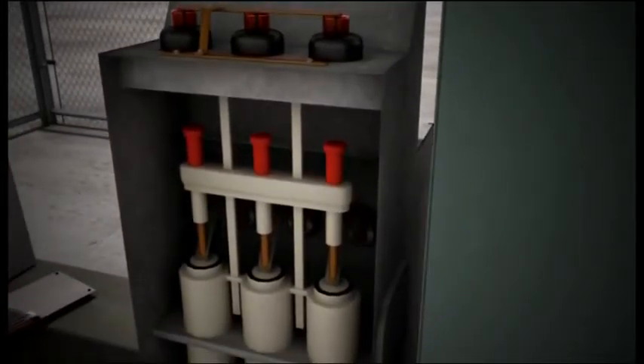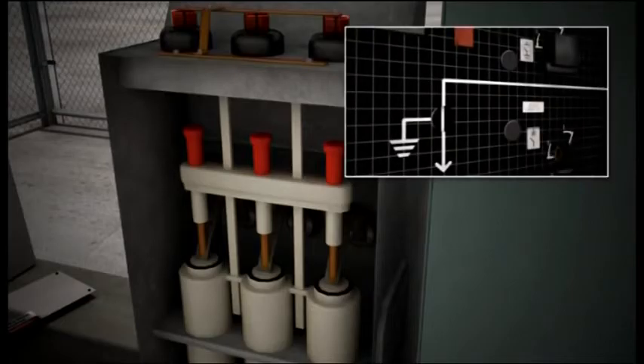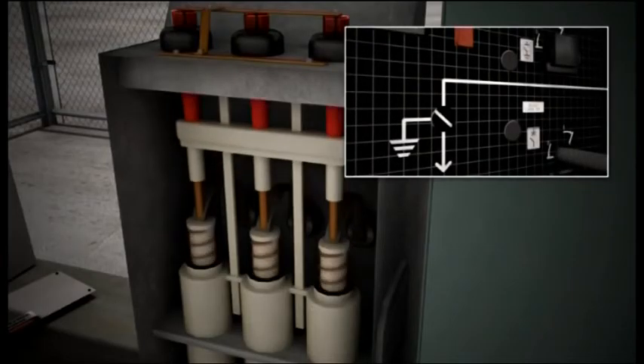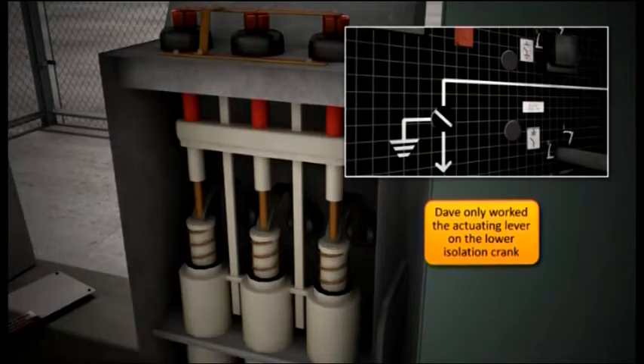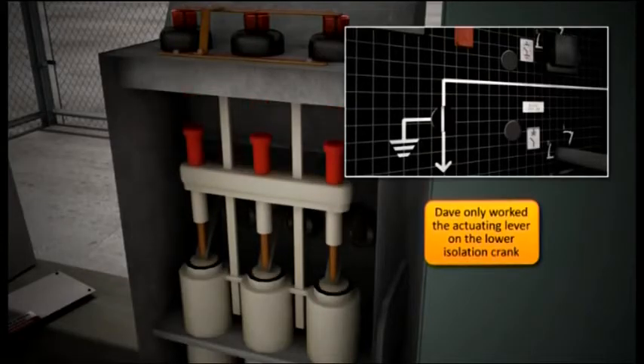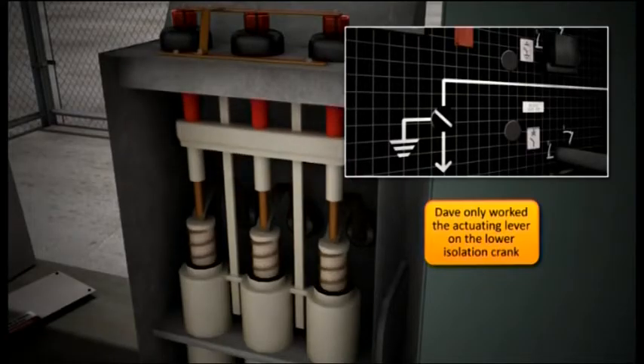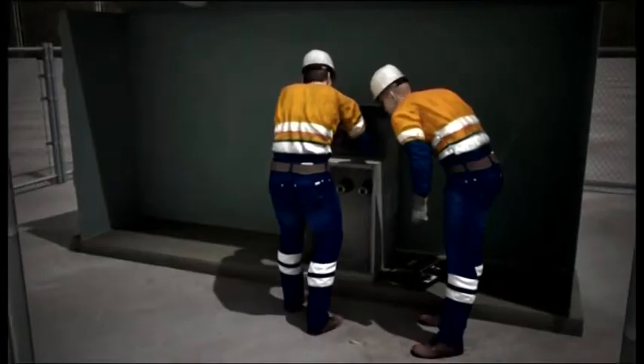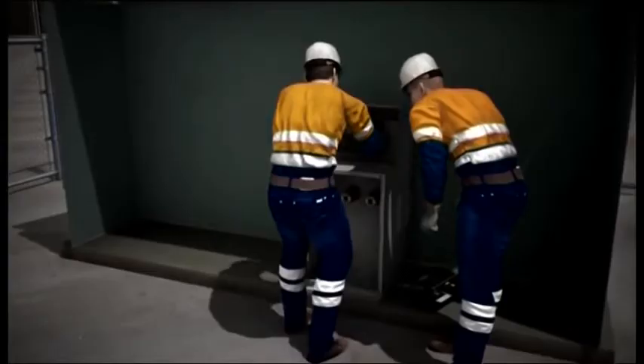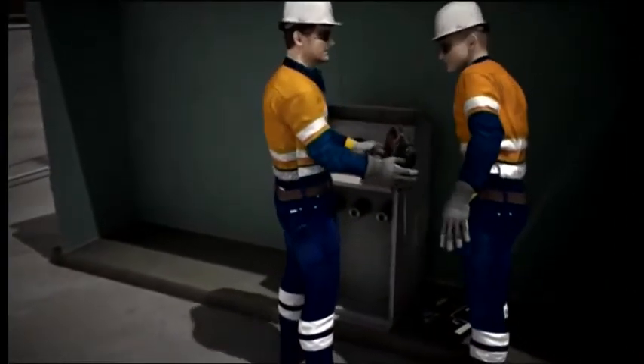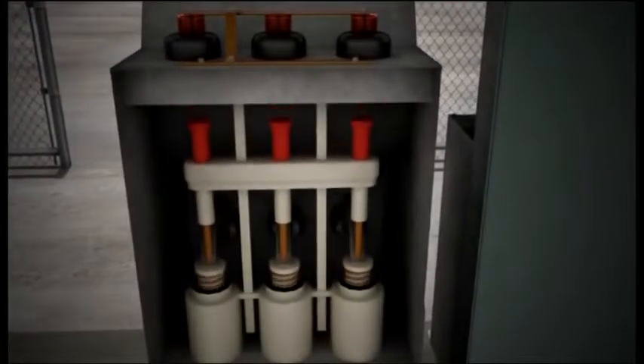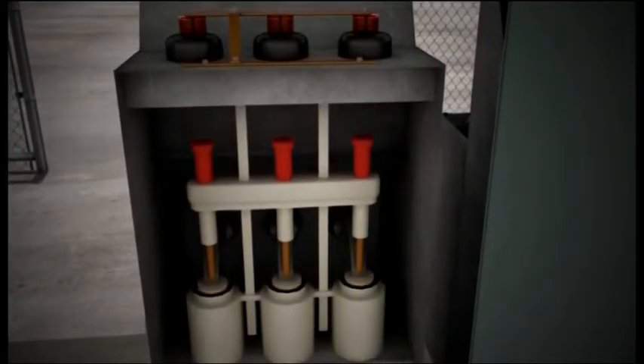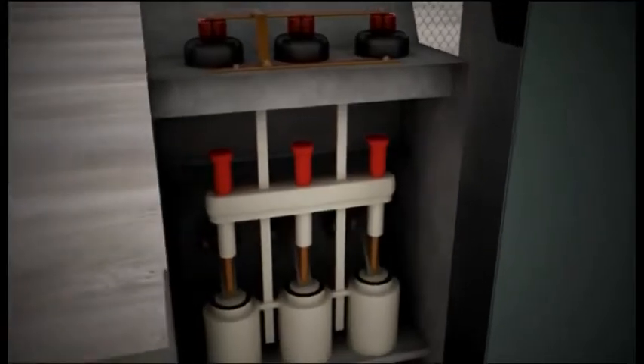Looking at the animation, we can see what happens when the actuating lever is cranked to de-energize the unit. Dave only worked the actuating lever on the lower isolation crank, causing the train to lift off the live ring main unit and sit in the middle, or open position on its tracks. Once the switching mechanism was removed from the control shaft, there was nothing to hold the train in place, and gravity simply acted to pull it downwards, eventually remaking contact with the live 22 kV ring main.